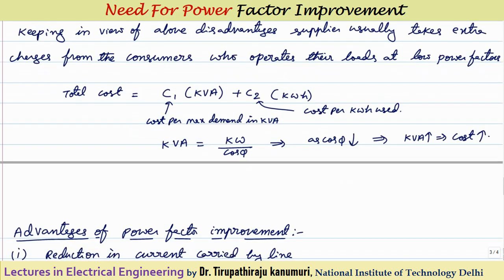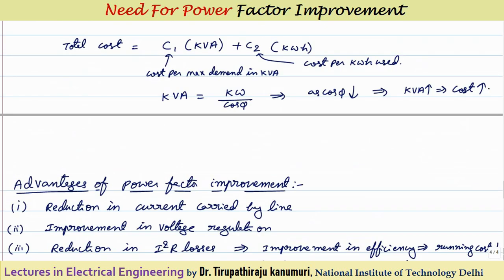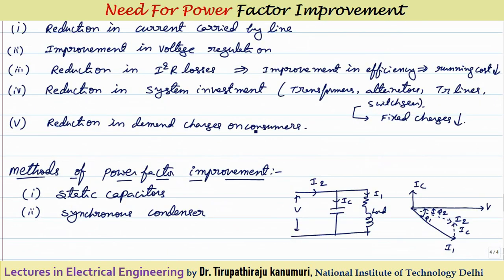Industrial consumers therefore install local setups to improve power factor. The advantages of improving power factor are: reduction in current carried by the transmission line, improvement in voltage regulation, reduction in I²R losses leading to improvement in efficiency and lower running costs, reduction in system investment since smaller transformers, alternators, transmission lines, and switchgear are needed, and reduction in demand charges since the C1 × KVA term decreases when cos phi increases toward unity.